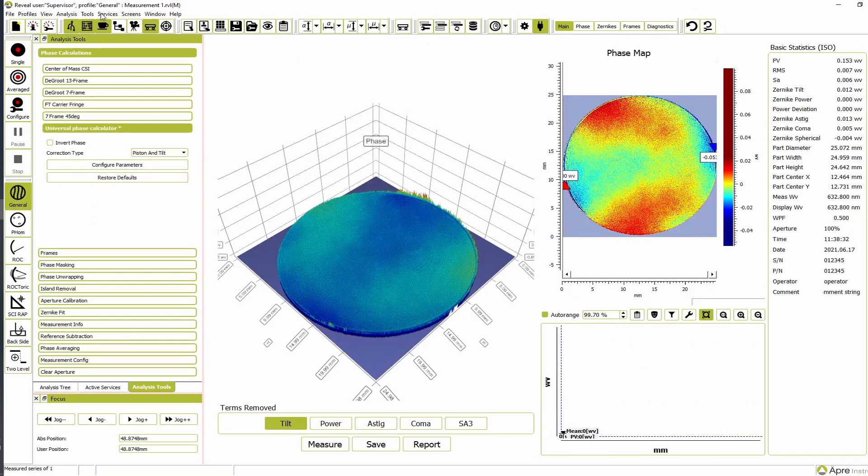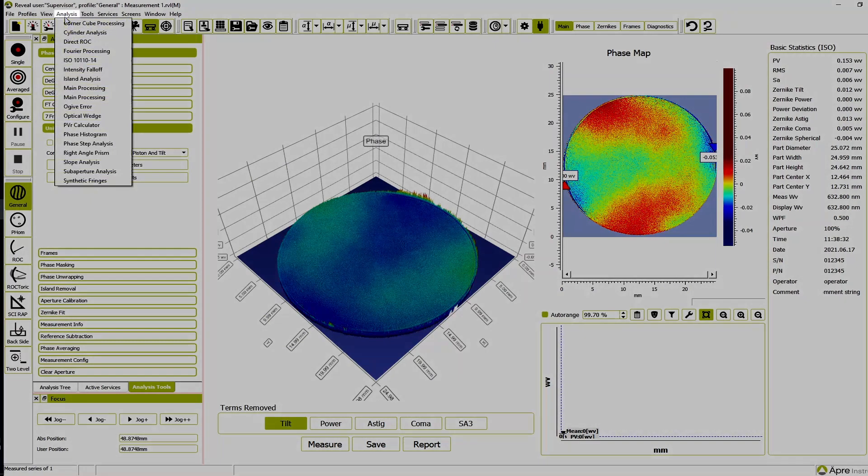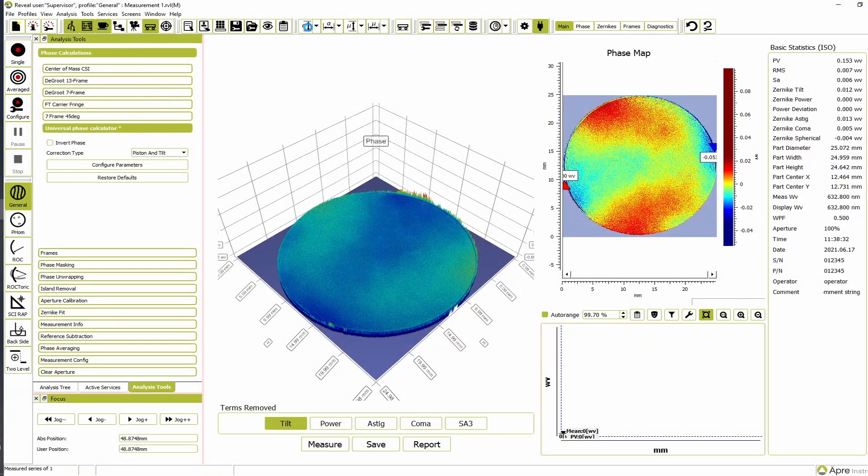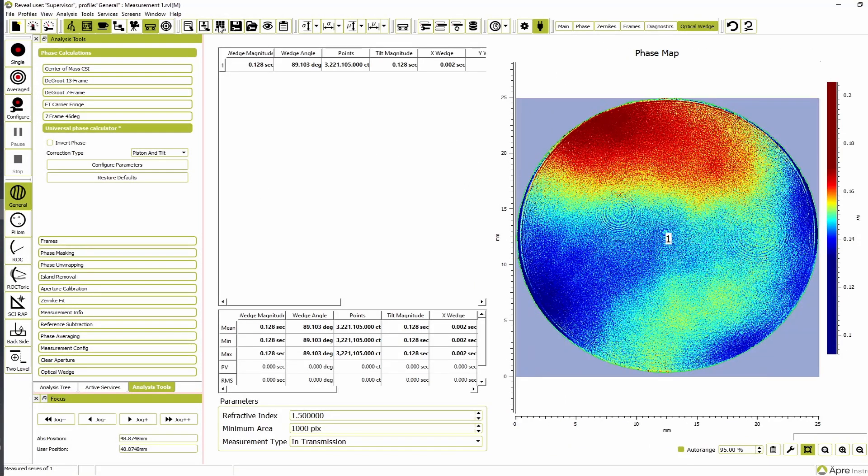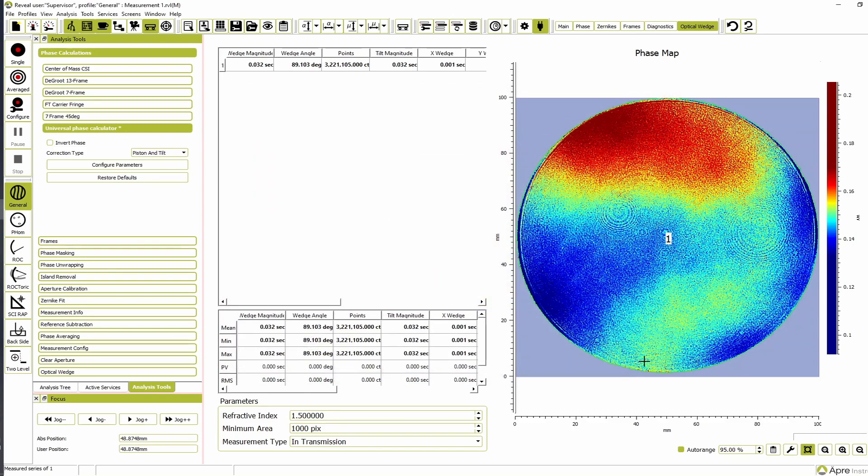Measure the reference flat. It is critical that you calibrate pixel size in order to have an accurate wedge measurement. First, open the optical wedge analysis screen from the analysis drop-down menu. Open the pixel calibrator and enter the diameter of the reference flat. Click Set Diameter and then OK.